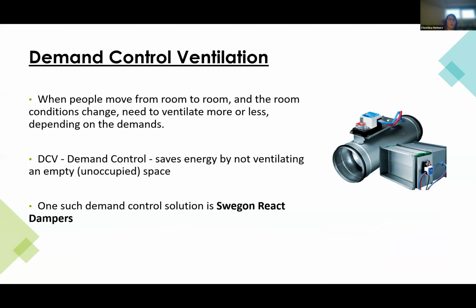Another option we talked about for this job, but didn't end up doing, is demand control ventilation. Let's say your central unit is controlling more than the six or eight rooms we have here. You might want demand control ventilation, putting Swegon React dampers at each space, on the supply side or both supply and return. That way, if no one's occupying that room, you don't have to ventilate it or provide conditioned air to that space, which would just cause unnecessary energy cost.